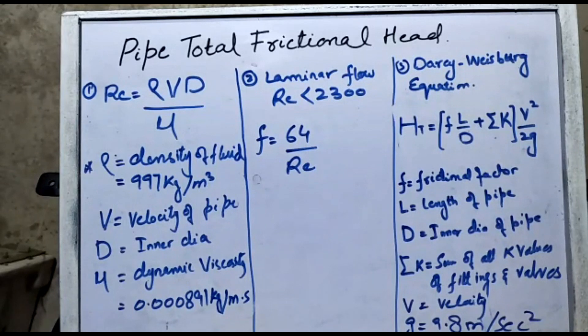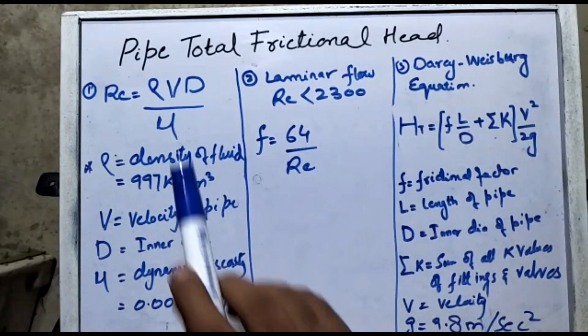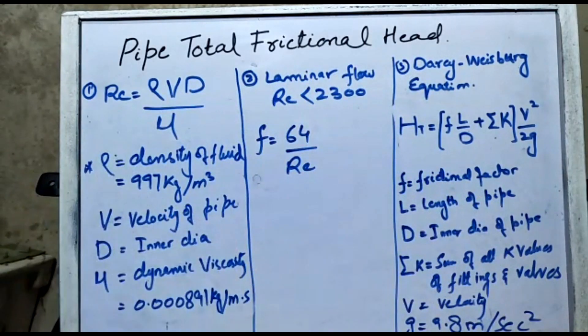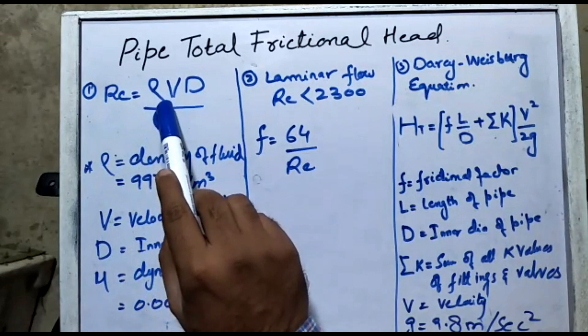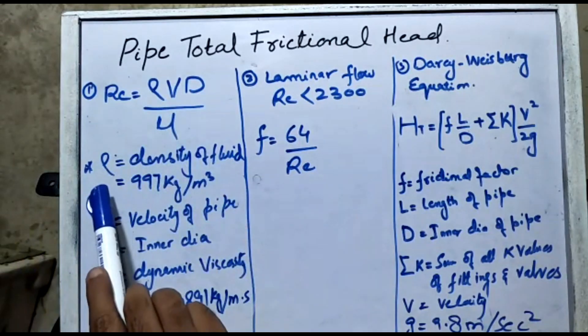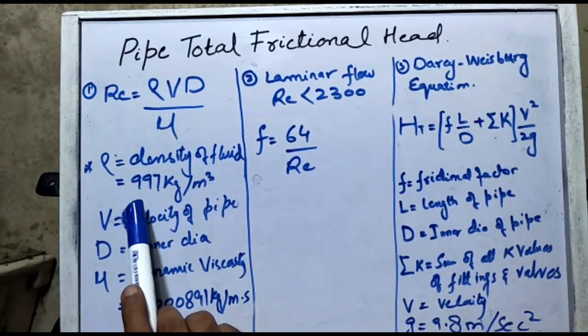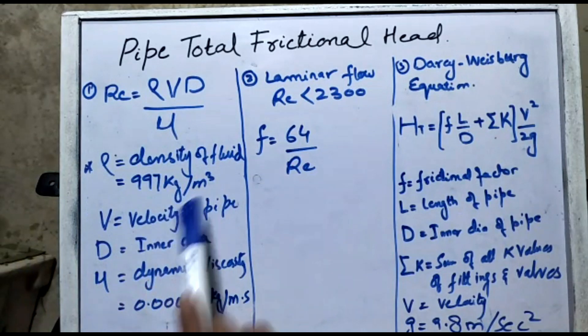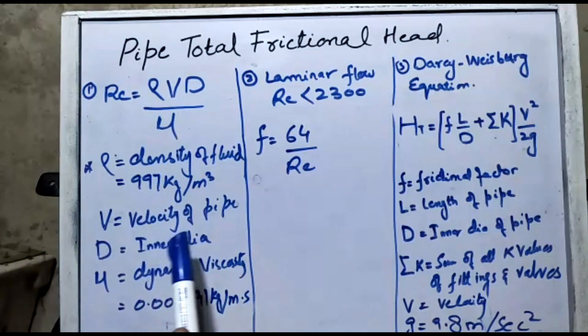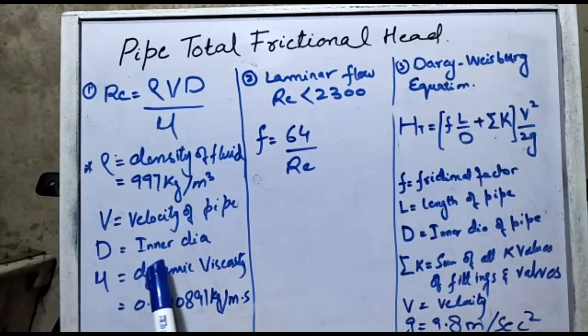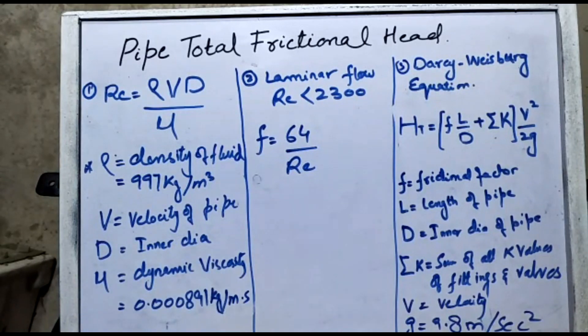We use three types of formulas in computing pipe total friction head. The first is the Reynolds number, which is equal to ρvd/μ, where ρ is the density of the fluid — for water its value is 997 kg/m³. v is the velocity of the fluid in the pipe, d is the inner diameter of the pipe, and μ is the dynamic viscosity, which for water is 0.000891 kg/(m·s).